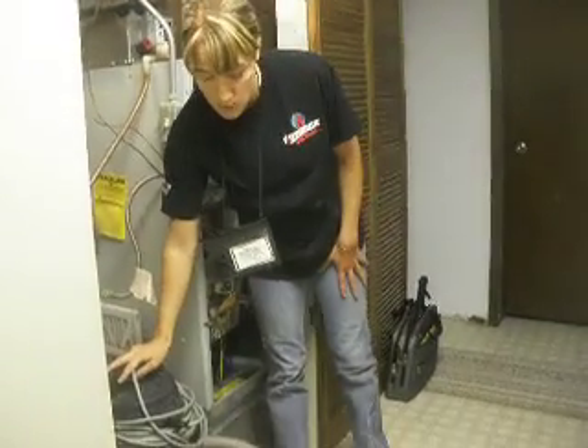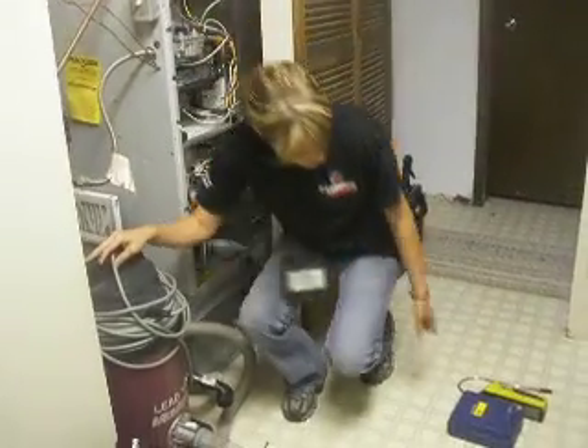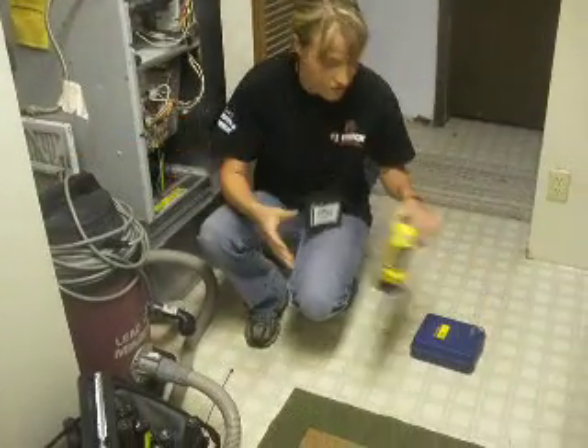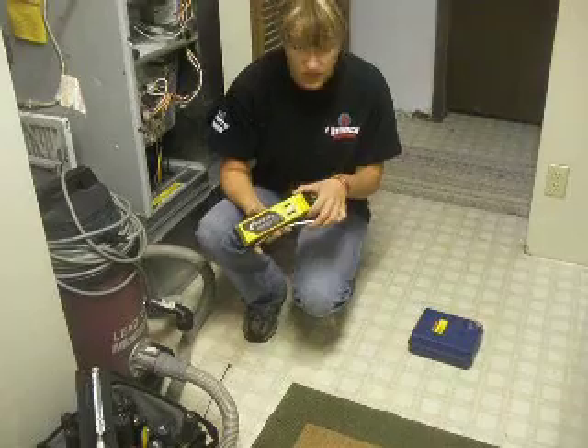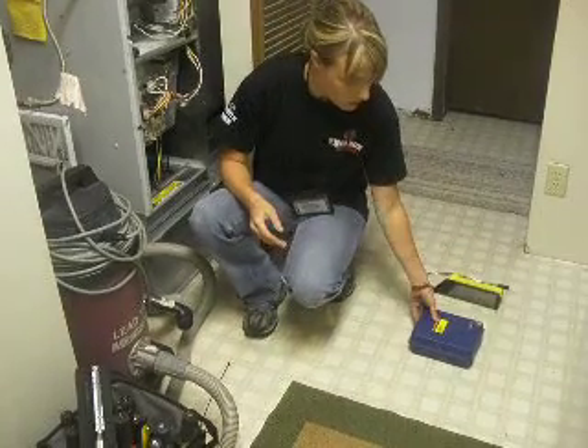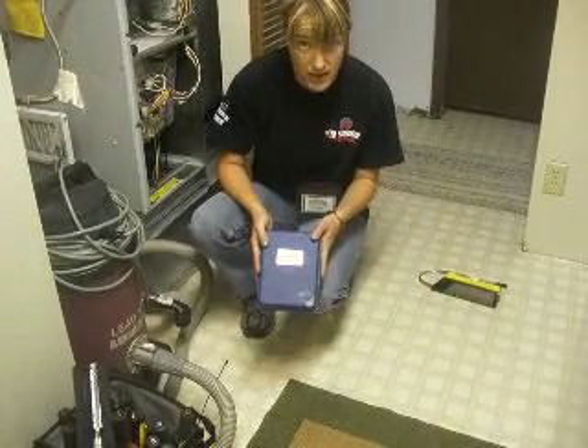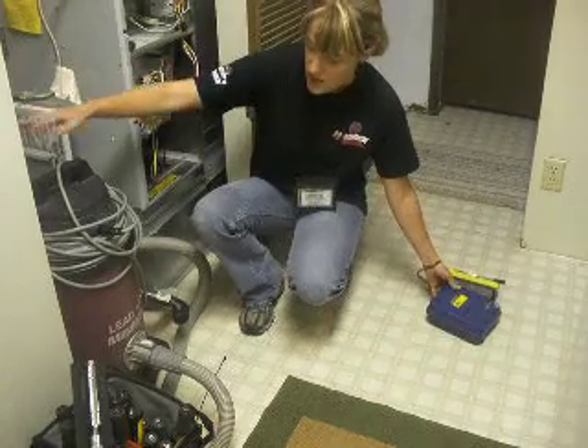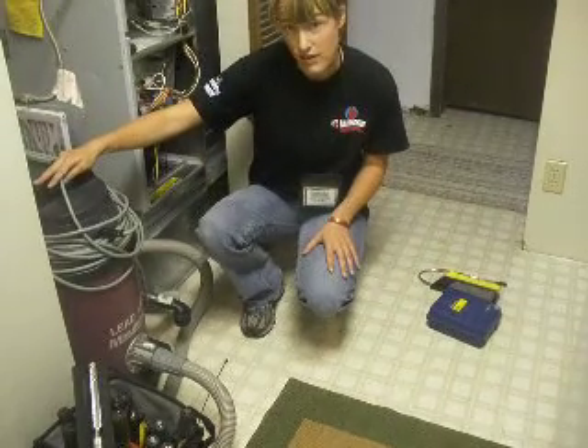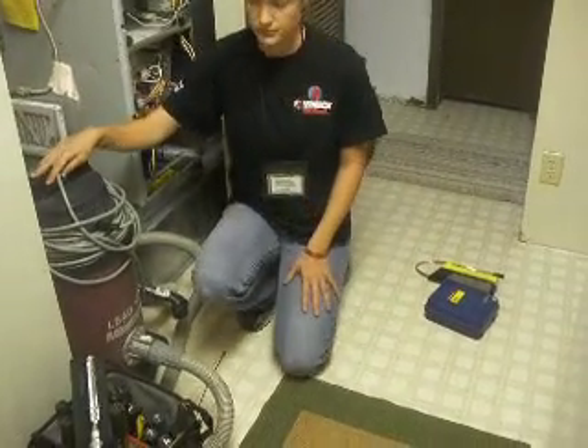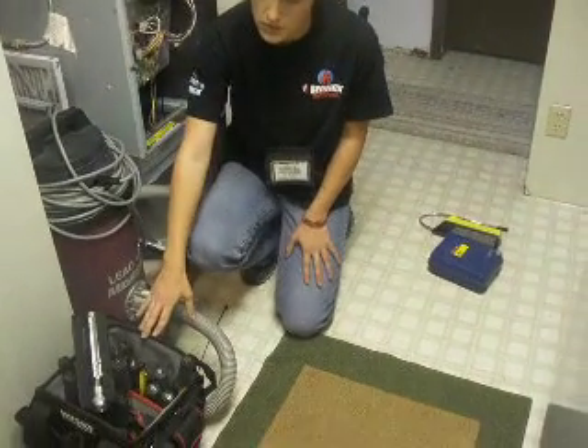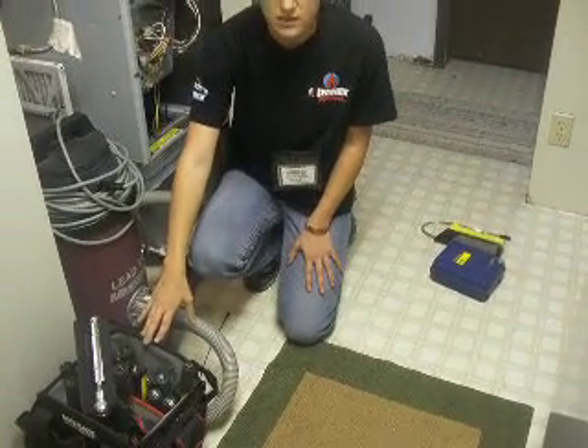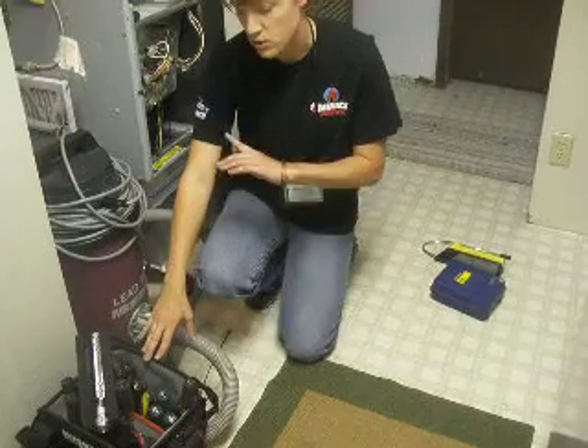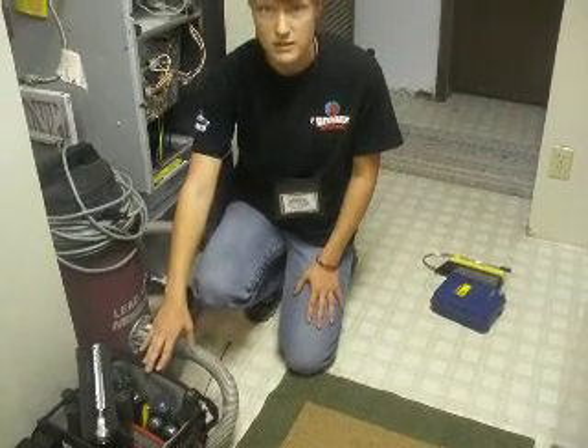Here are some of the tools that I will be using during the cleaning and the inspection. I have my leak detector for natural gas, my manometer for gas pressure testing, the lead-safe critical area vacuum I will use to clean, various hand tools, mirrors, and my lights that I will use to dismantle the furnace and inspect the heat exchanger.